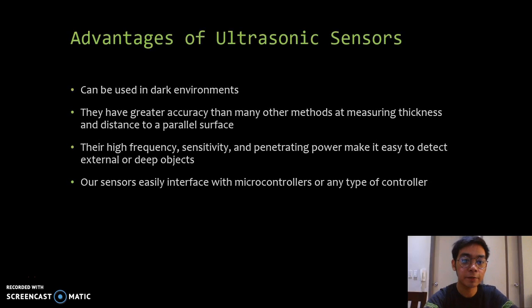So, here are the advantages of an ultrasonic sensor. Number 1, they can be used in dark environments. Number 2, they have greater accuracy than many other sensors in measuring thickness and distance to a parallel surface. Number 3, their high frequency, sensitivity, and penetrating power make it easy to detect external or deep objects. And the last one, the sensor easily interfaces with microcontrollers or any type of controller.